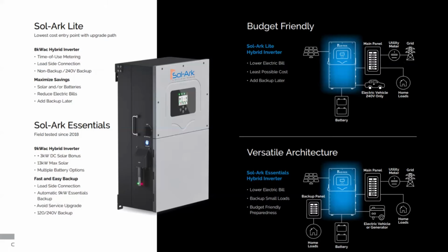You can shave a little bit of table stakes off of the buying cost by going with a cheaper inverter and abandoning the backup capability of the system, maybe adding it down the road. So we do have a low-cost Sol-Ark Lite inverter. It is not capable of 120/240. It's only capable of 240. Advanced users might be able to figure out ways to expand that.